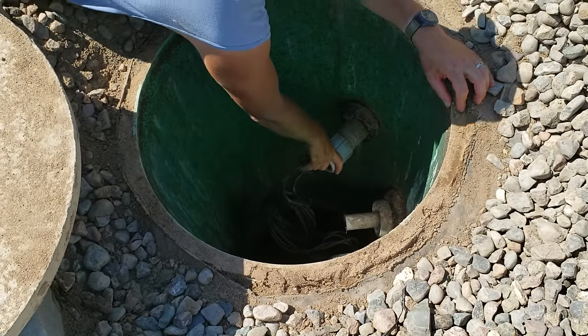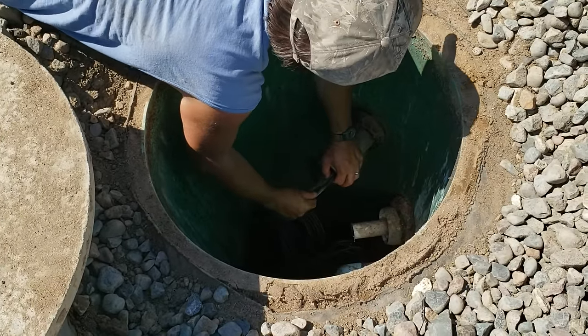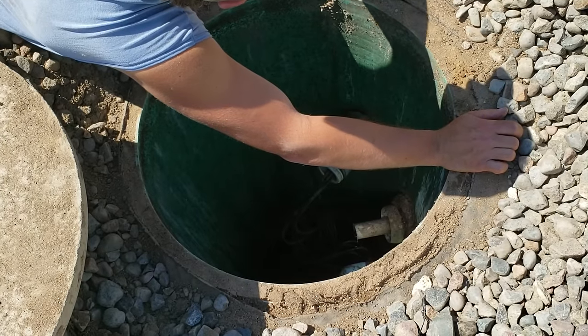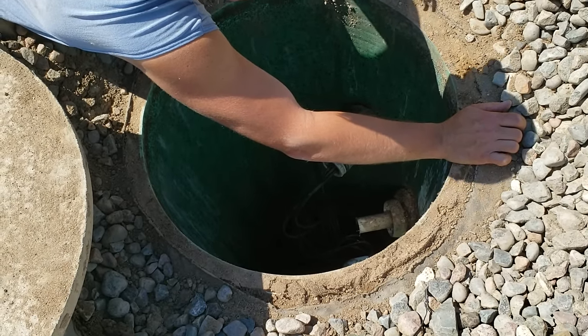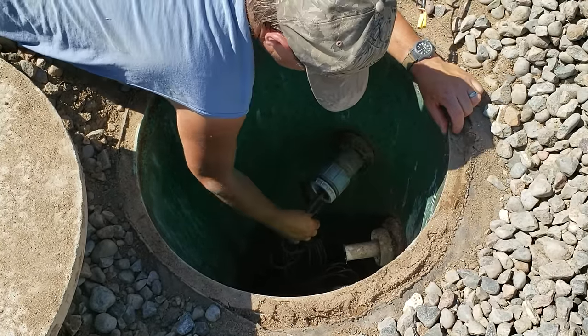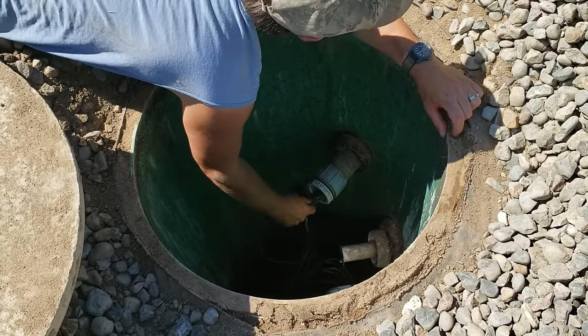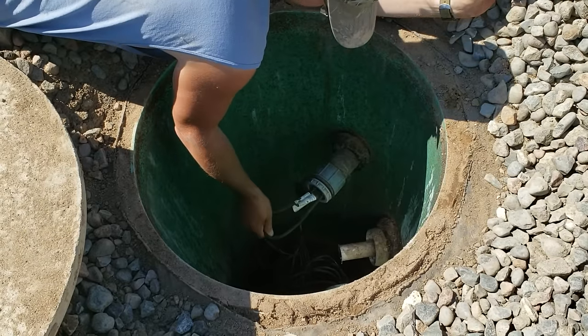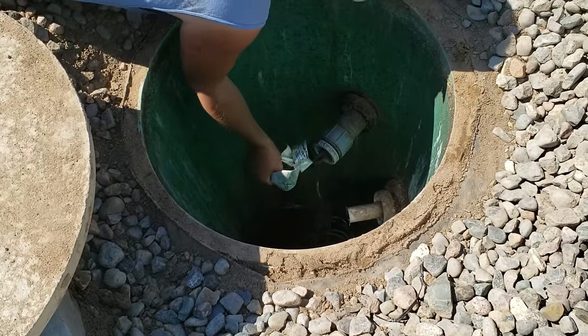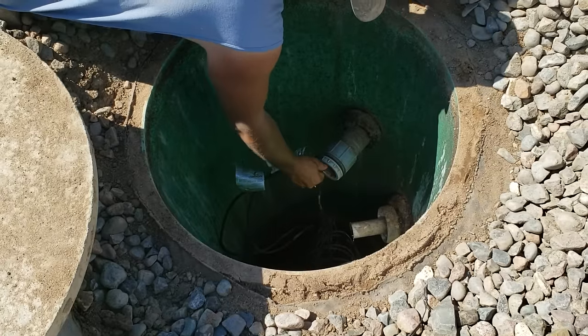You really should never lift your pump by the electrical cords, but the pump that's in here is dead. There is a ring down on this pump, which I found out once I got it up, but they didn't leave a cord to actually lift the pump either. When these guys installed this mound 11 years ago on the farm, they just cut a few corners. I wish they had given me a disconnect and hooked a cord to the pump at the bottom.